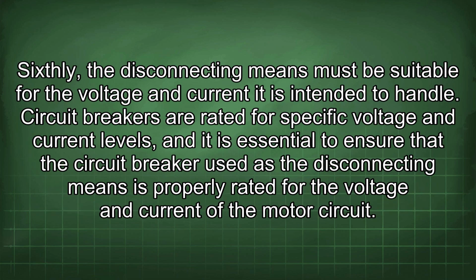Sixthly, the disconnecting means must be suitable for the voltage and current it is intended to handle. Circuit breakers are rated for specific voltage and current levels, and it is essential to ensure that the circuit breaker used as the disconnecting means is properly rated for the voltage and current of the motor circuit.